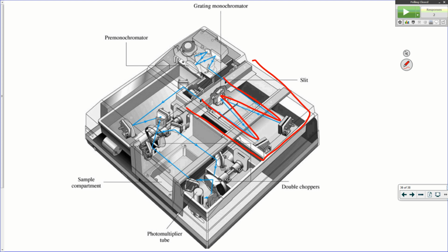You can't make that guy too small, okay? Because of the amount of separation of the light that you're going to ultimately get going from the focusing mirror to this length on the focal plane where the exit slit is, you maximize that to get the best separation. So if you get close, you're not going to get good separation. So these are always going to be larger boxes. You can't miniaturize that design. The diodes, however, can be miniaturized. You can make them much, much smaller. But typically, the higher the resolution, the bigger the footprint the instrument's going to be. And that's just the trade-off that you have to have.